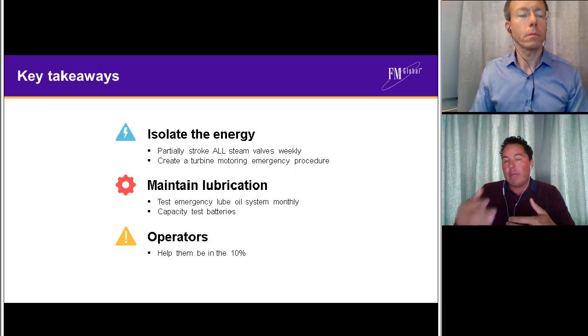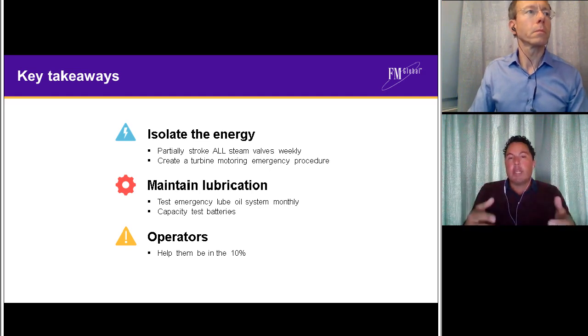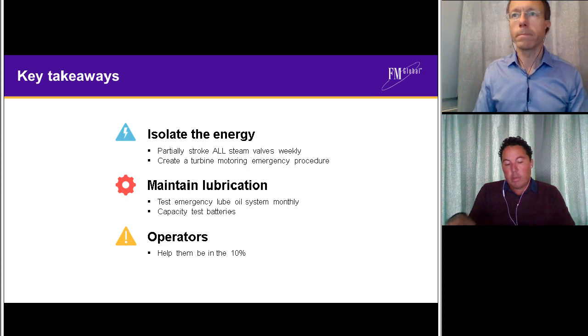between those two points, so that you've got maximum chance of the oil that is discharged from the emergency lube oil pump finding its way onto the bearings and maintaining lubrication until the turbine runs down.